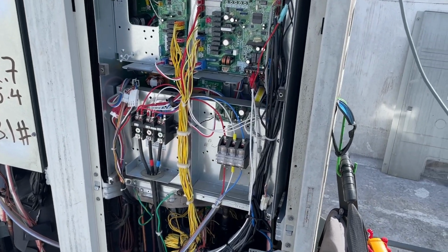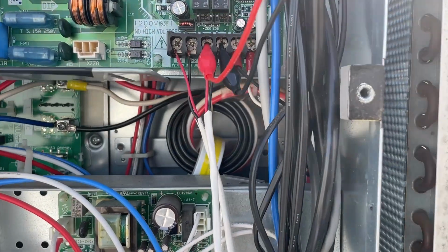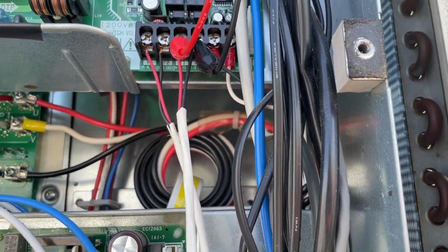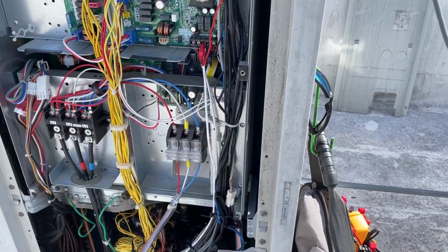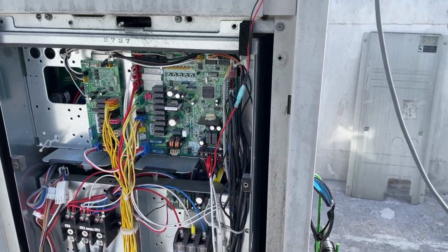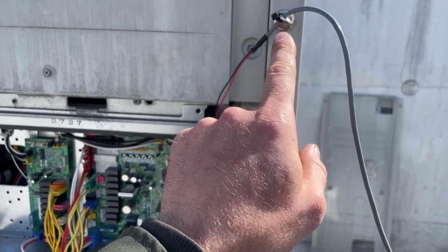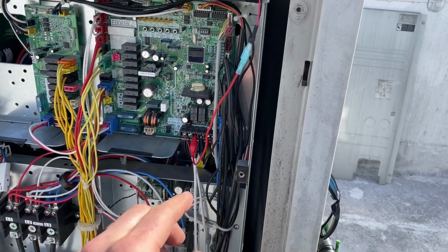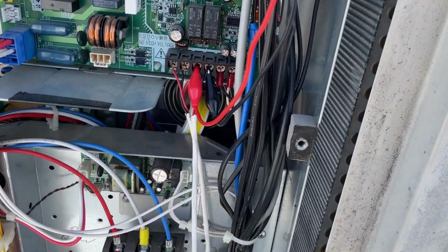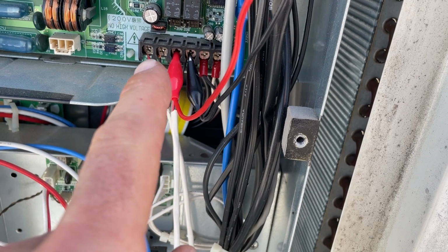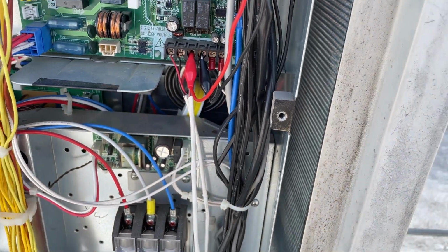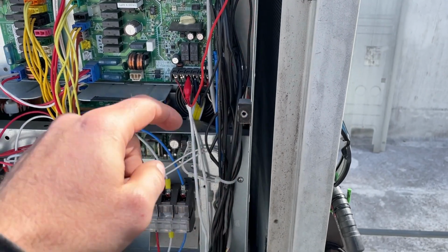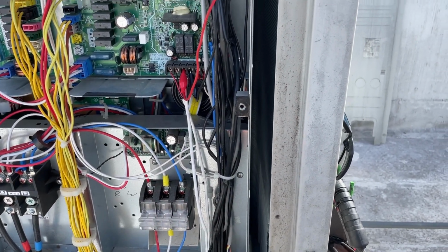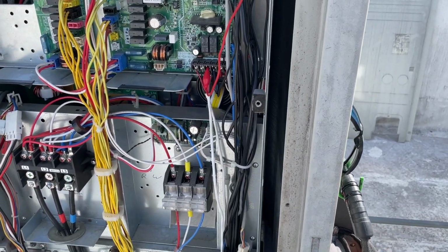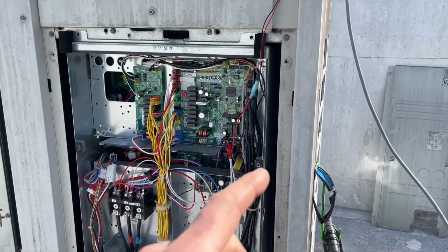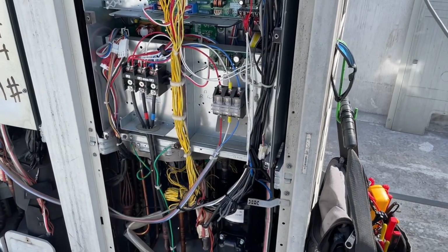Now what I'm doing here is I'm connected into F1 and F2, those are my comm lines. The setup I like to use is I have a magnet on my cable and I put it up higher here. If these happen to detach, and I've found that the small alligator clips by far work best on these little screws, if they happen to detach I like to have the cable up high so they don't drop into mains, that would be very bad for the old service checker. But I've got my cable up there just running back to the service checker.